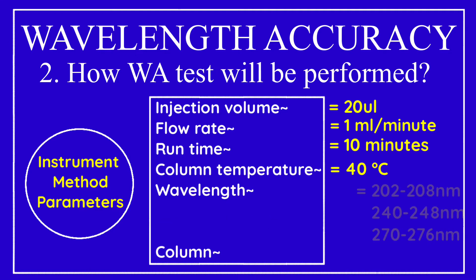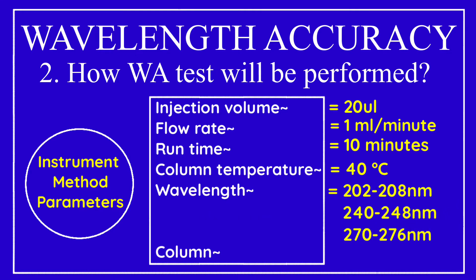Three sets of wavelengths are used during the wavelength accuracy test: 202 to 208 nanometers, 240 to 248 nanometers, and 270 to 276 nanometers. Generally, a C18 column with 150 mm length, 4.6 mm diameter, and 5 micron particle size is used for the wavelength accuracy test.